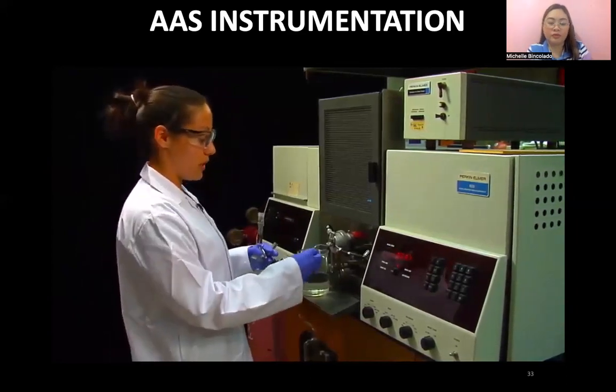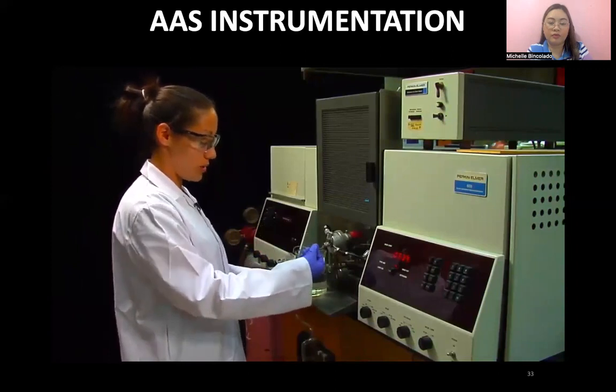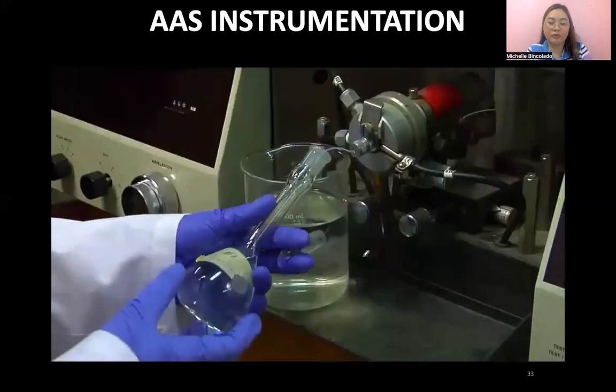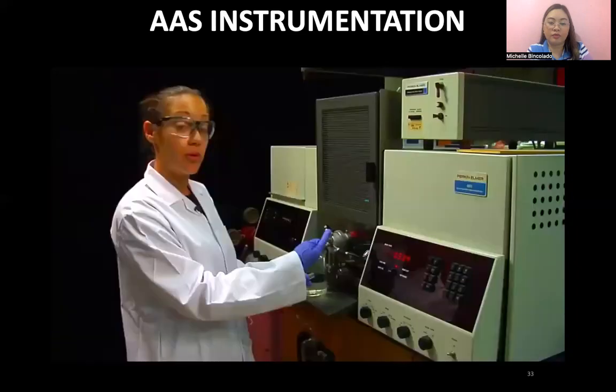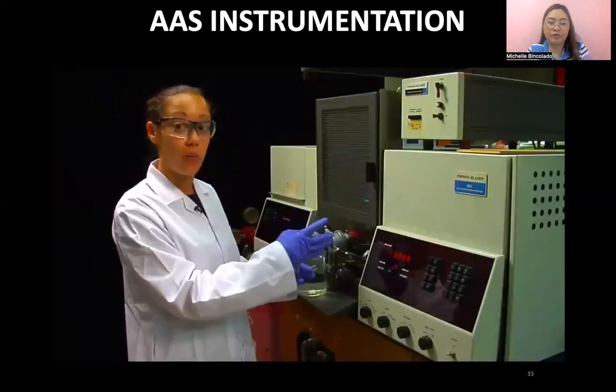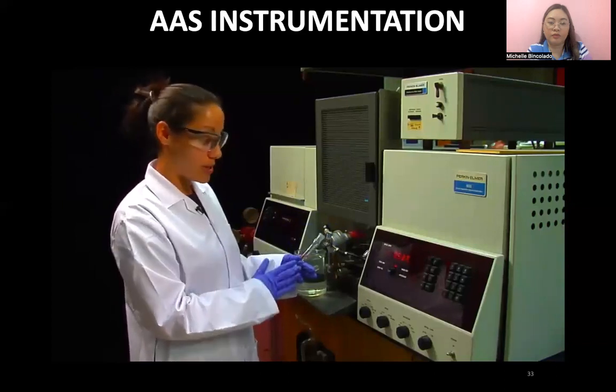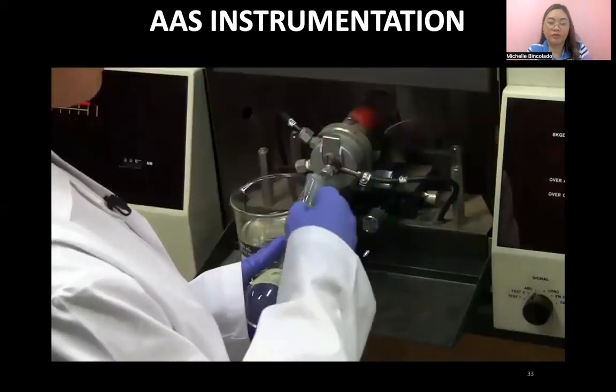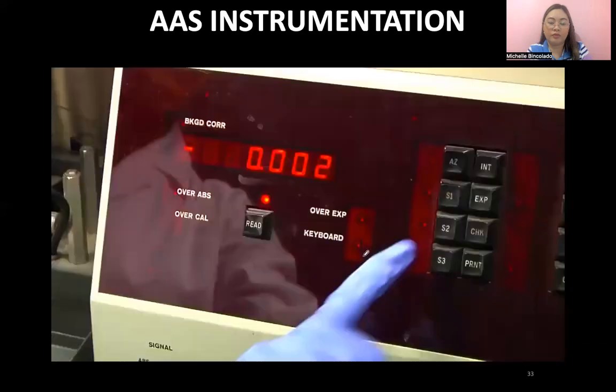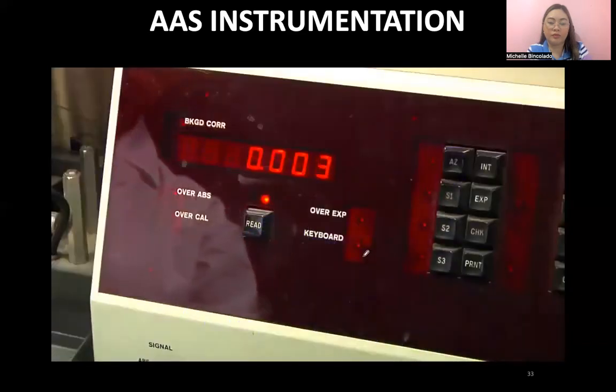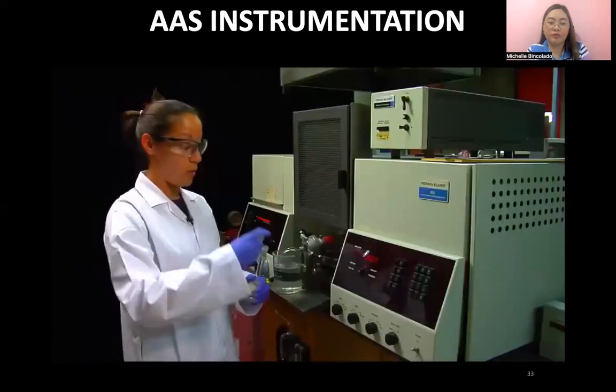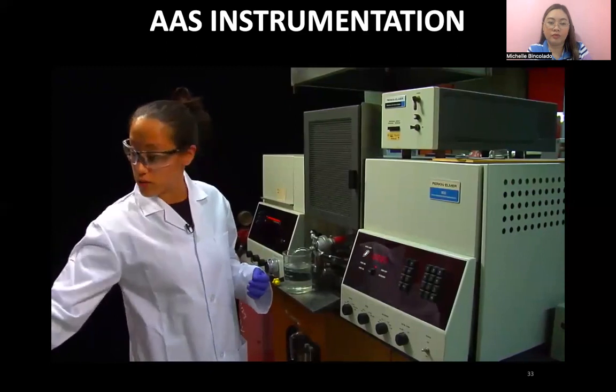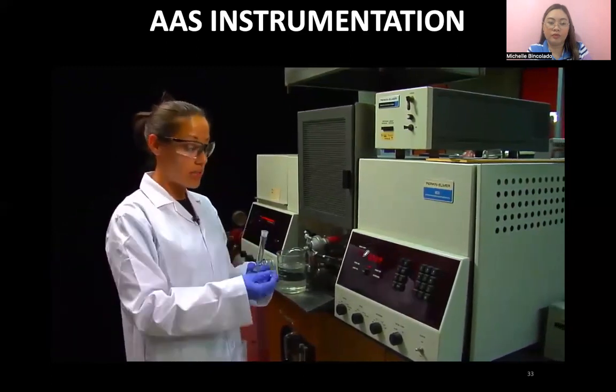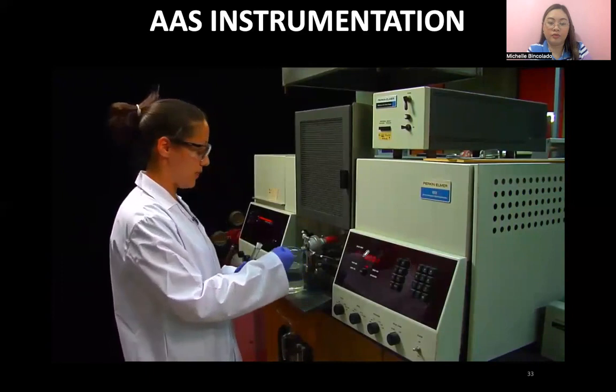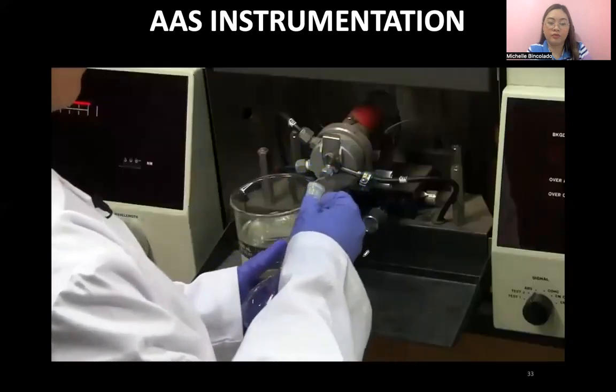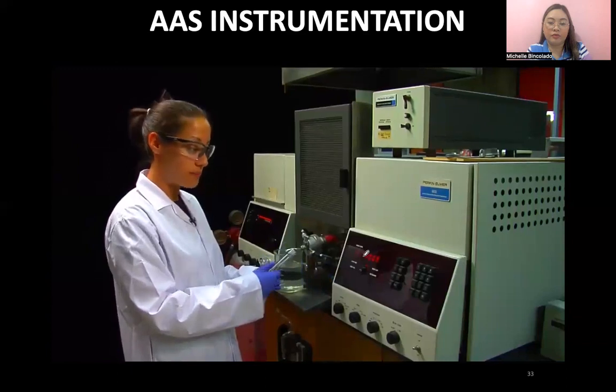It's really simple. This is just your nozzle. You insert the straw into your sample, and it automatically sucks up your sample and aspirates it into the flame to create atoms. This is how we atomize your sample. Once your sample is being ingested by the flame, press auto 0 to make sure your background is corrected for. Once that's accomplished, it's a matter of measuring each standard relatively quickly, since absorbance is an instant reading. Just sticking that in there, you'll see an increase in your absorbance.